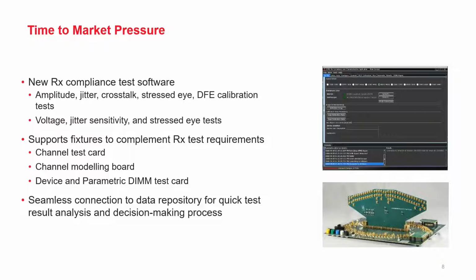For that, of course, there are a lot of system impairments that we need to incorporate, and something that's been developed to enable this is a new test fixture. On the bottom right here, this is what we call the CTC2, or channel test card. This exposes and routes out all the necessary high-speed signals, all the DQ signals, the DQS, the clock, and control signals like reset and alert. Those are signals that we can calibrate to using automated calibration software. This will apply the limits per the specifications and make this receiver testing much easier to implement. And I think the main takeaway from this is we've really gone away from direct probing measurement at the far end of the channel, to now the measurements being referenced instead at the ball of the part.